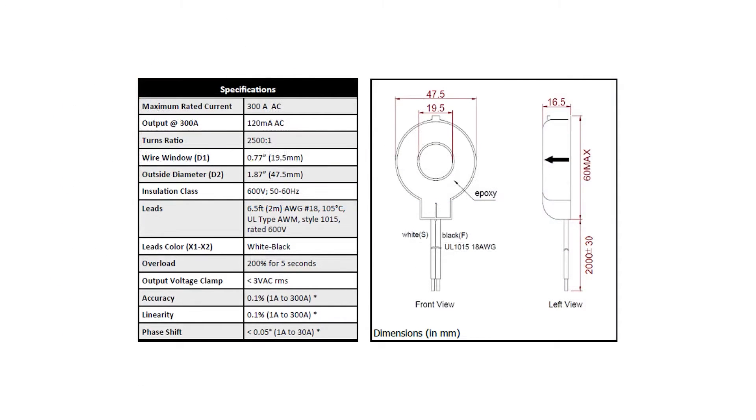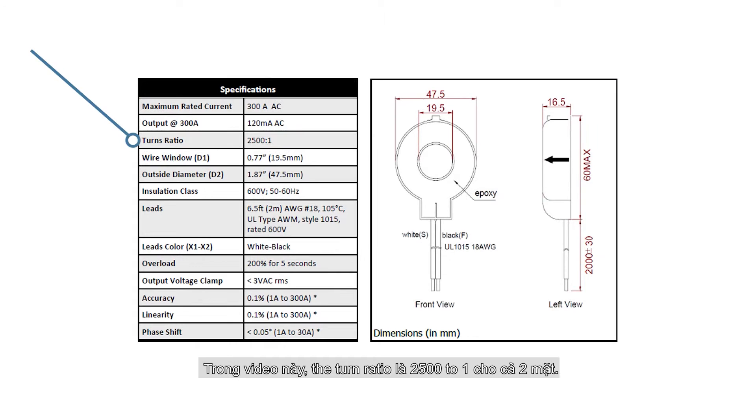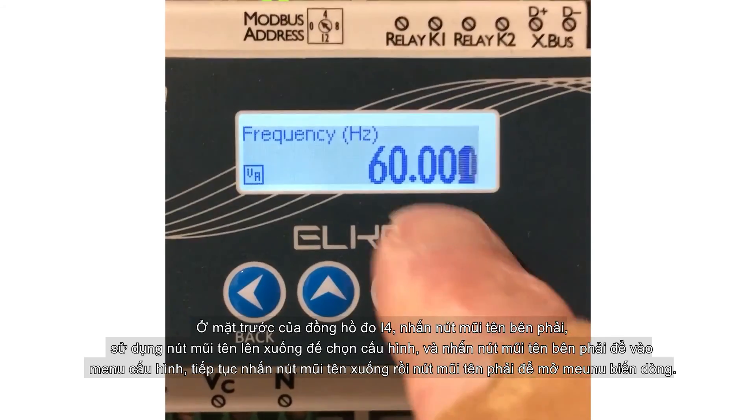The turns ratio for the CTs being used must be set. For the MCTA CTs used in this video, the turns ratio is 2500 to 1 for both. On the front of the Elkor meter, press the right arrow, use the down arrow to select configuration, and then the right arrow to enter the configuration menu.